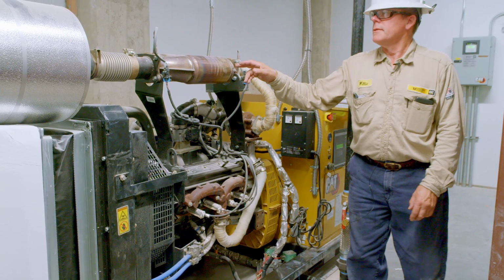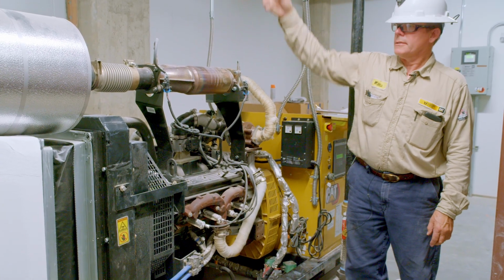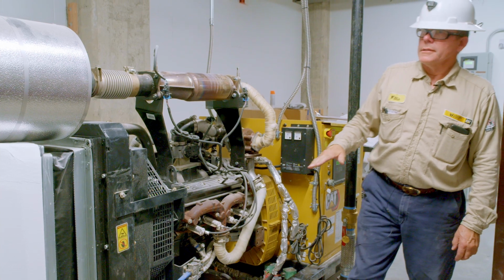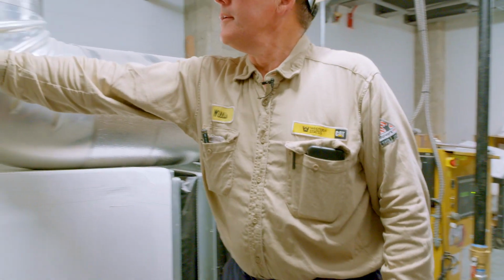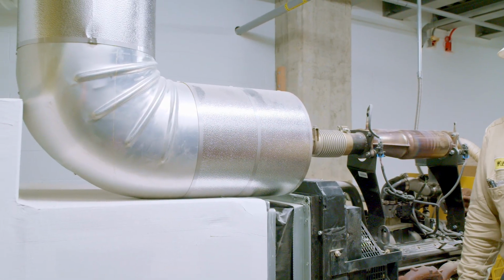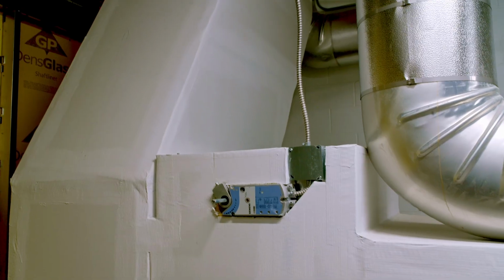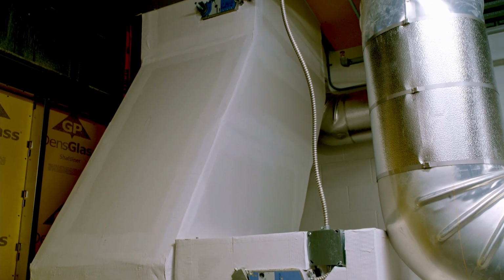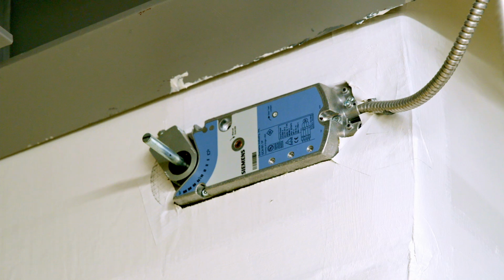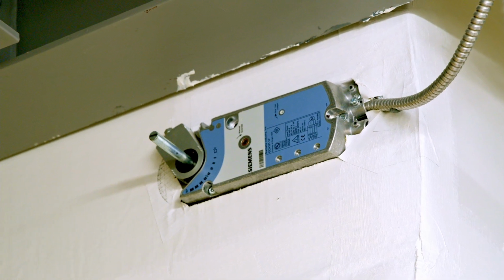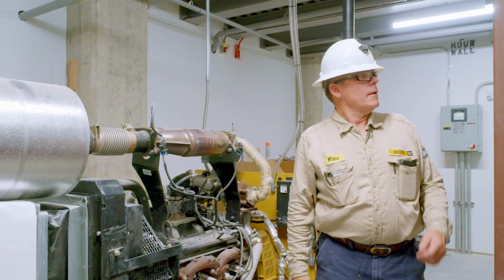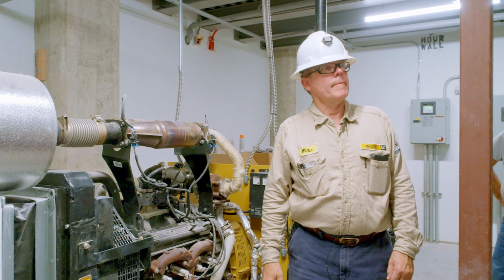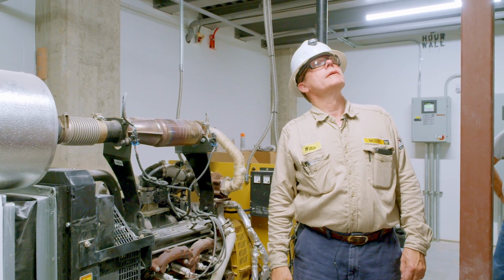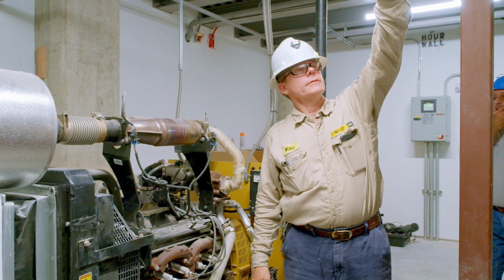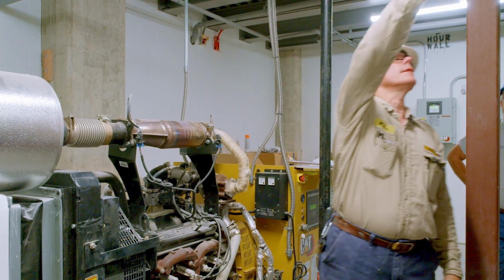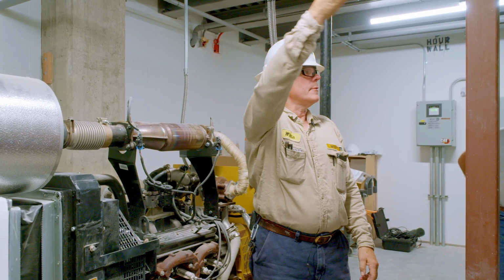Your catalyst goes out the exhaust. There's a louver here to recirculate air in the room, and your outlet louver is up near the ceiling. They're controlled sometimes by thermostat, but here it's just controlled by the generator running - when it runs, it opens. Your fresh air intake is controlled the same way, with a louver right here to bring fresh air in.